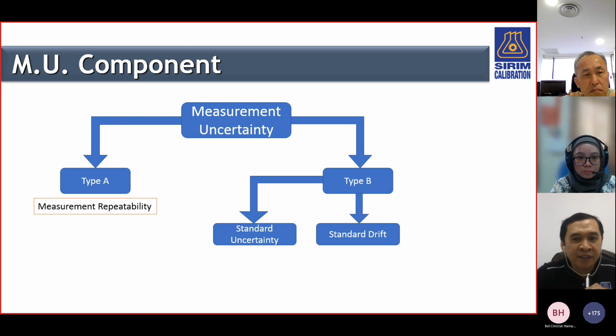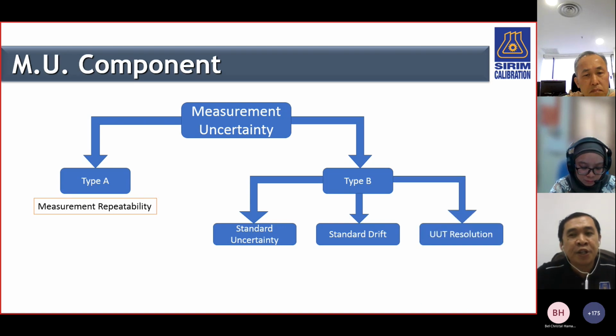If you can recall just now, drift means the previous year's MU reading. So how much is the difference between last year's reading and this year's reading, and it's applied as a measurement uncertainty on type B. And number three is UUT resolution, unit under test resolution. Unit under test resolution means the user's equipment.